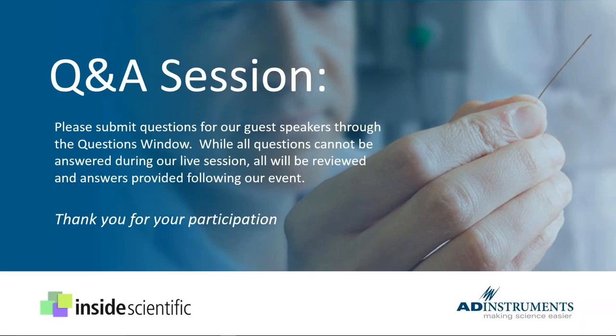You certainly can, and some additional information to this is, yeah, you can certainly record from all the segments and gather that information, even if you make a decision ahead of time about how many segments you're going to be using. But what you should also consider is that each of those will affect the way your calibration works in a multi-segment catheter. So if you're going to plan in advance to have a certain number being used during one portion of the study, and perhaps you have to expand that, keep in mind that each of those has a volume associated with them. So you want to make sure you retain that information so you can apply it later.